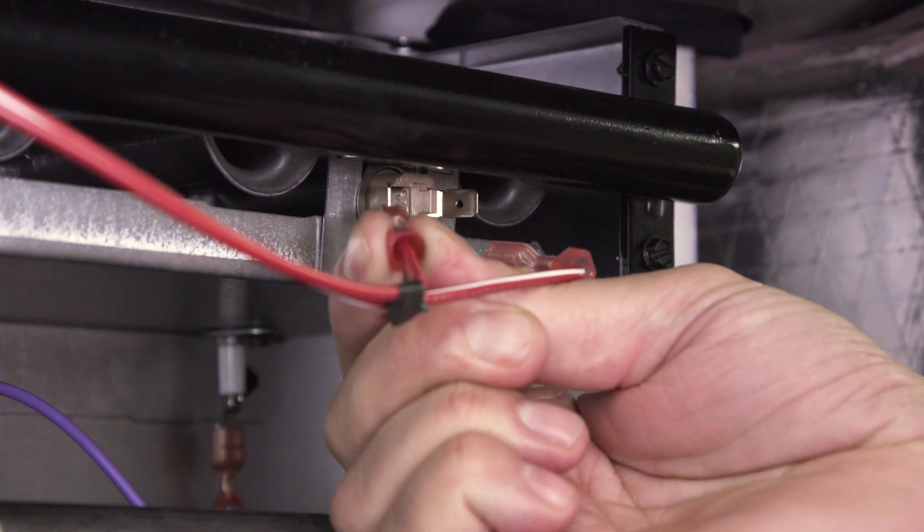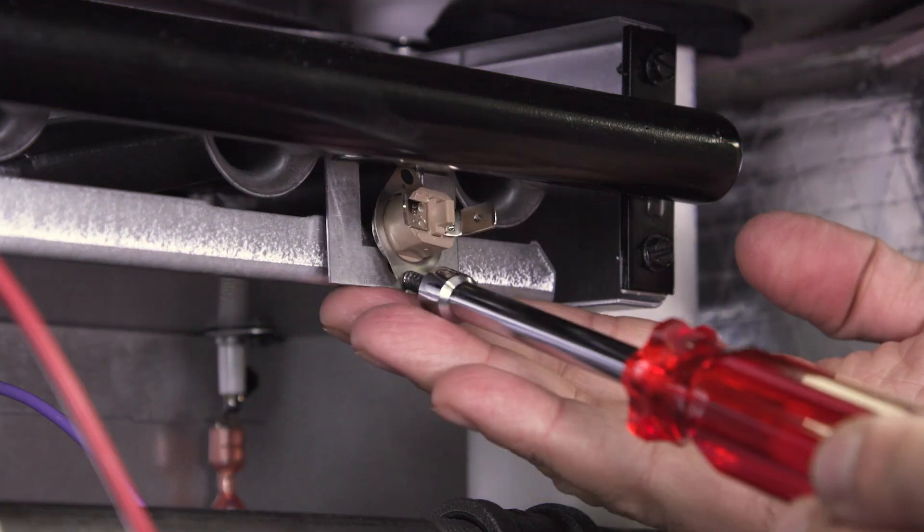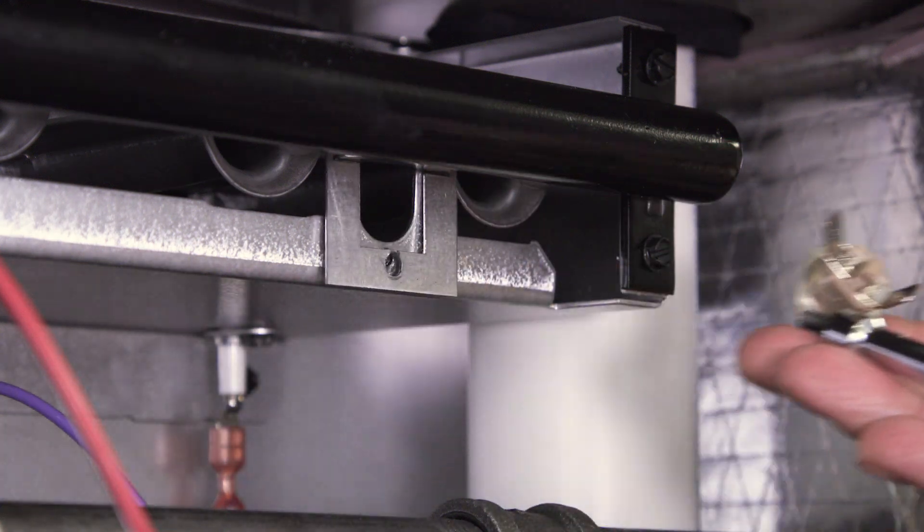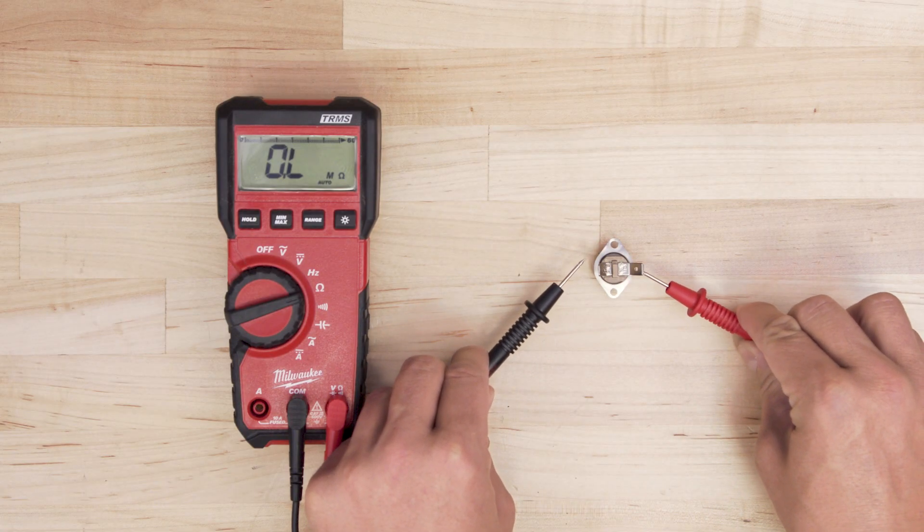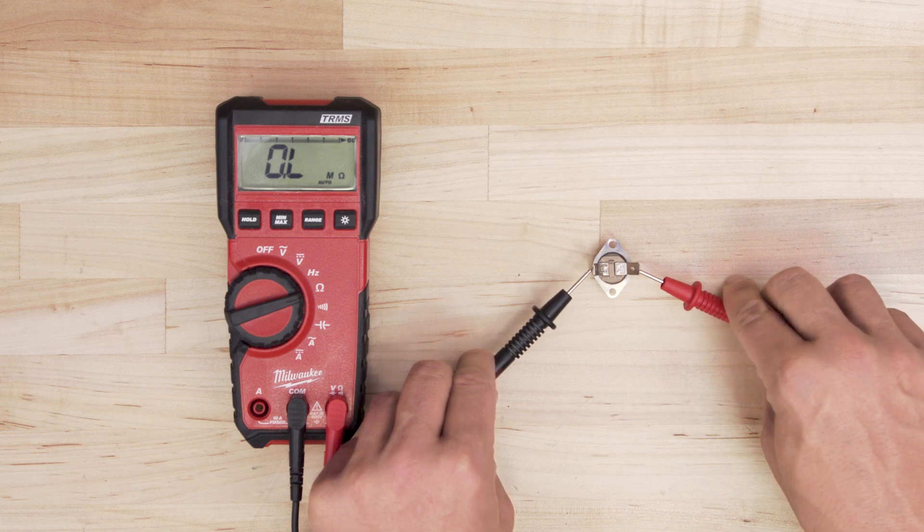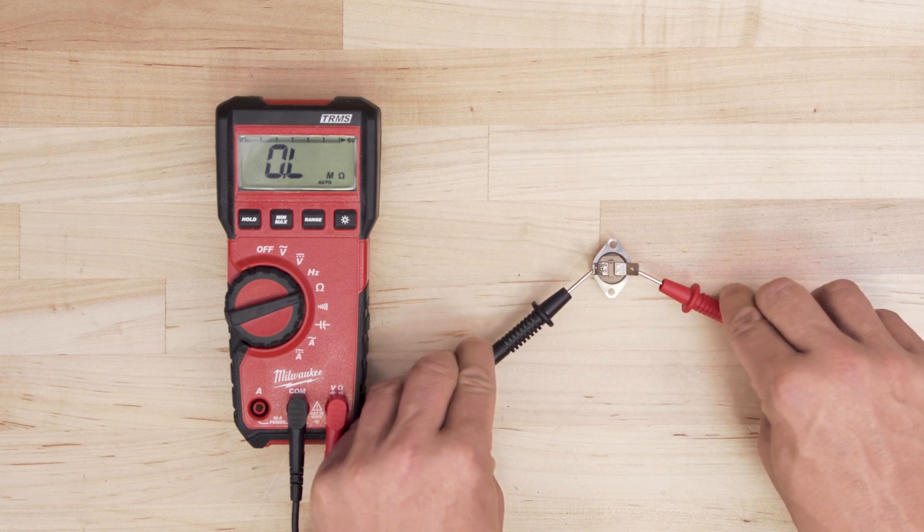If there's no sign of a flame rollout, then the flame rollout switch might be defective. Test the switch for continuity. If there is no continuity, then replace the flame rollout switch. If there's continuity and the flame still doesn't stay lit, then call a professional.